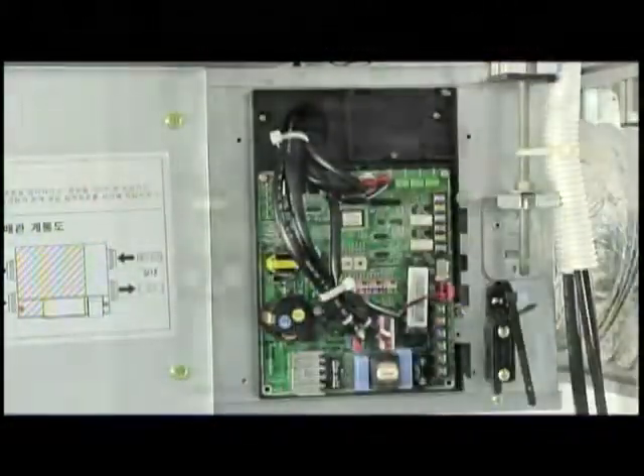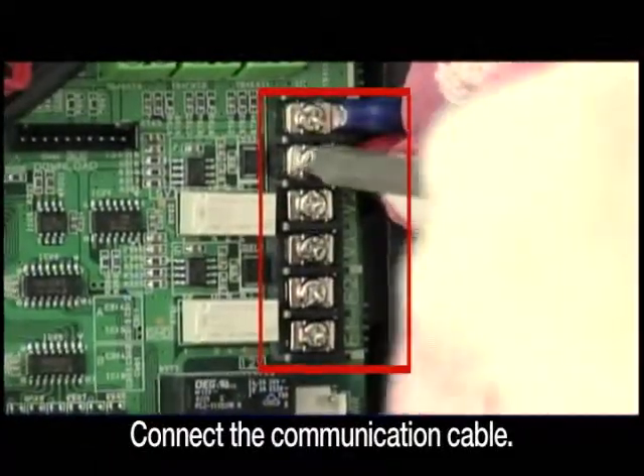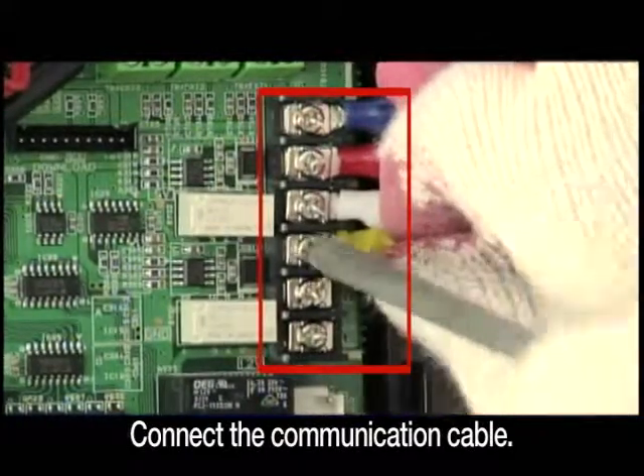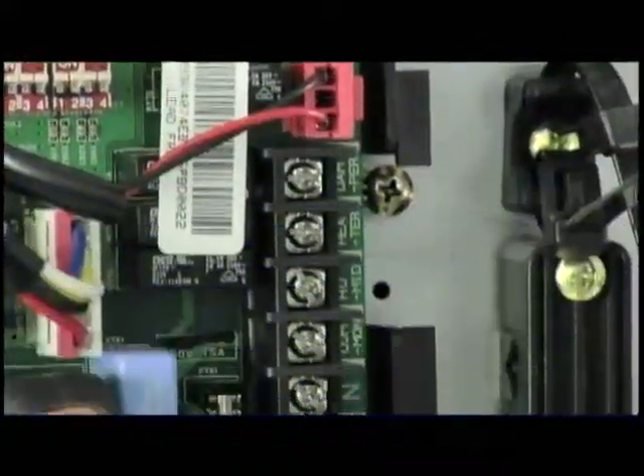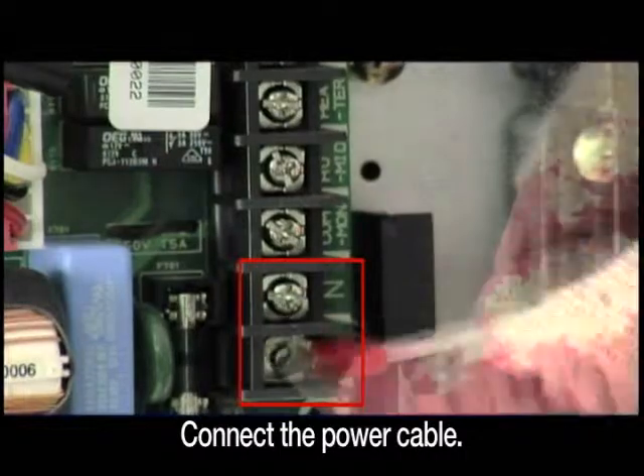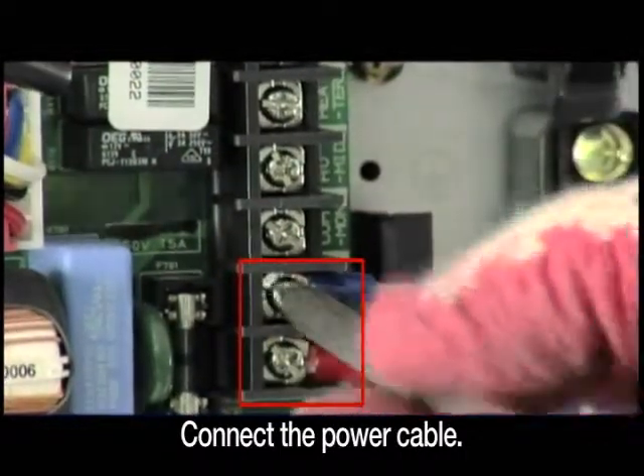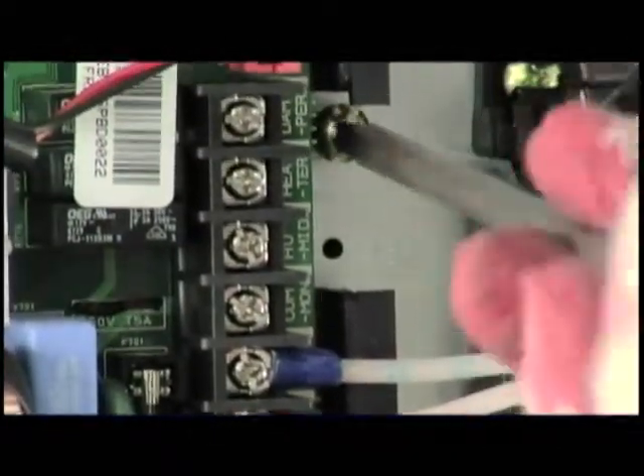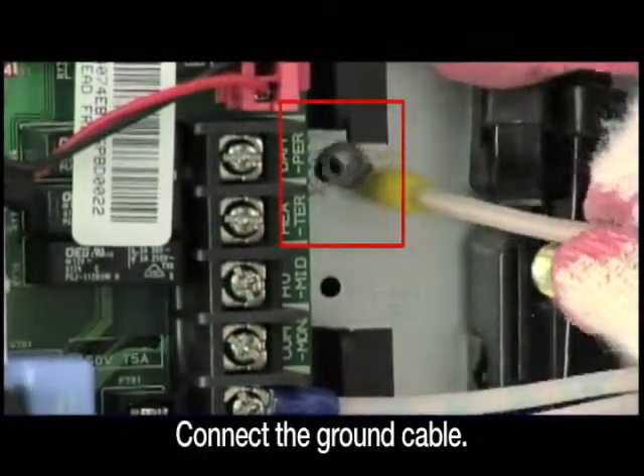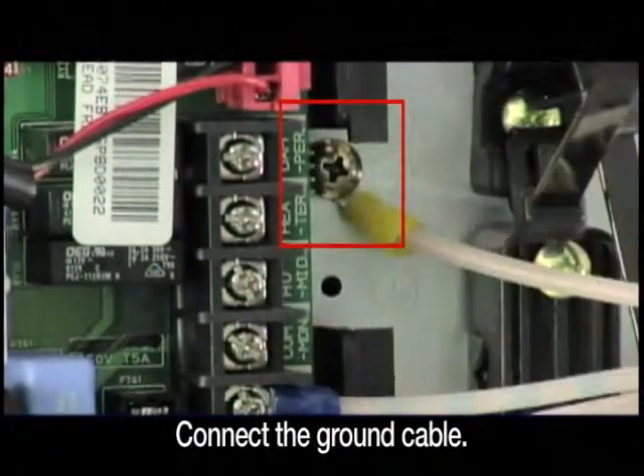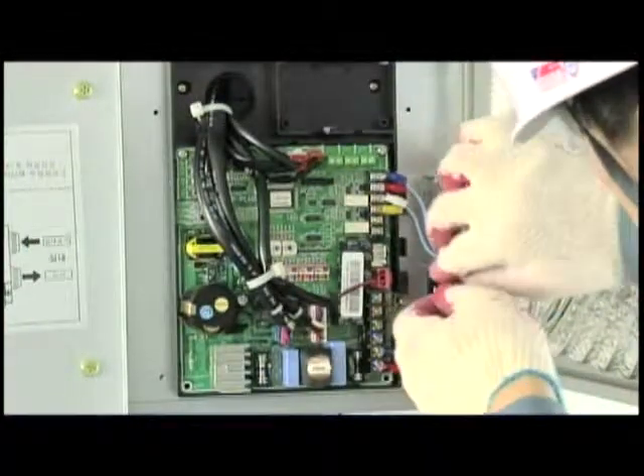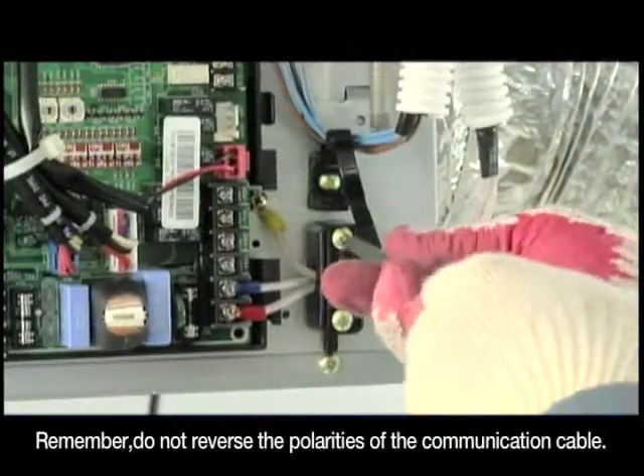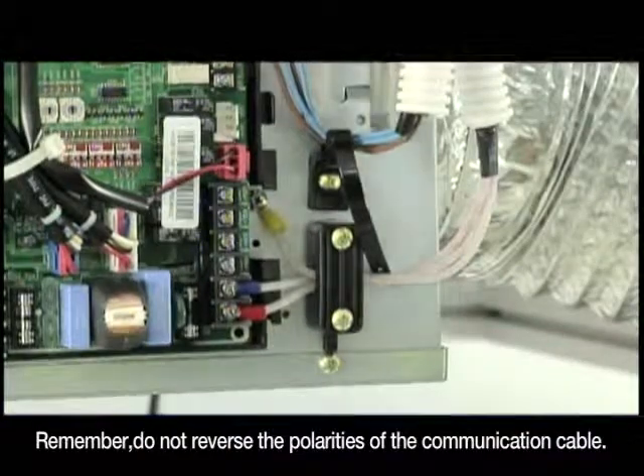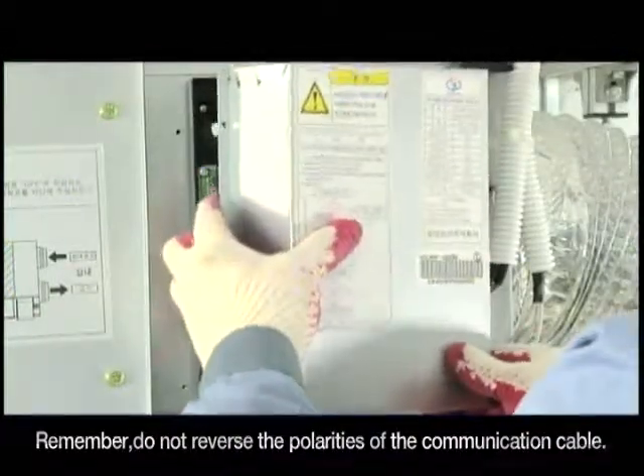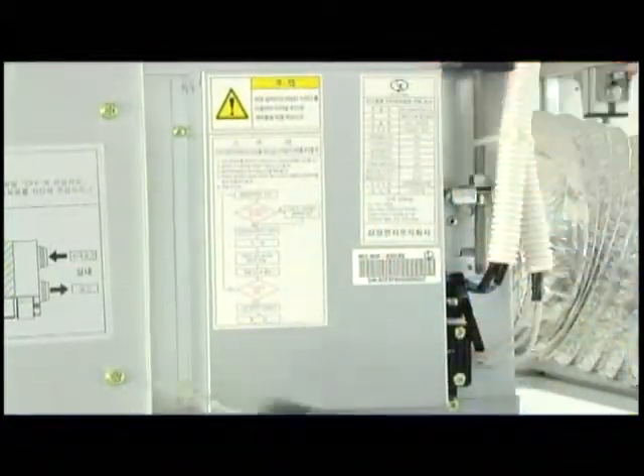After connecting the duct to the ventilator, you can connect the remote controller cable and power cable. When connecting the cables to the terminal block, you need to use the terminal that satisfies the specifications. Wiring of the power and communication cables is very critical in terms of product operation. If the wrong wire thickness is selected or the power and communications cables are misconnected, then it can damage the product function. Make sure wiring is correct.